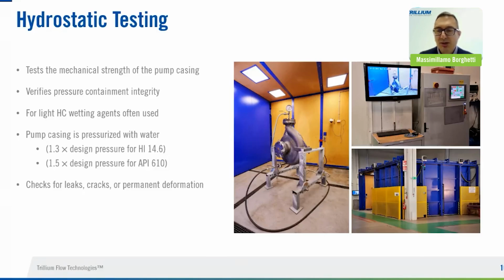Generally, as Sam already said, different standards define the hydrostatic test pressure in a different way. A couple of examples: HI 14.6 defines the hydrostatic test pressure as 1.3 times the design pressure. In a different way, the API 610 standard defines the hydrostatic test pressure as 1.5 times the design pressure. Finally, there is a case that has to be considered.